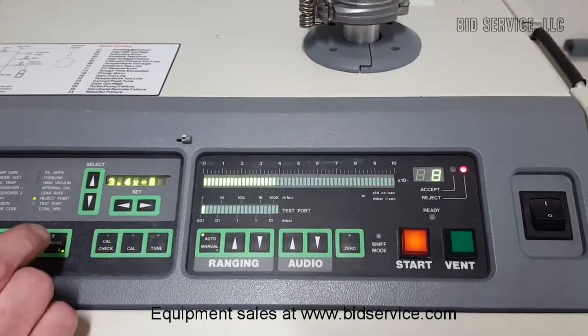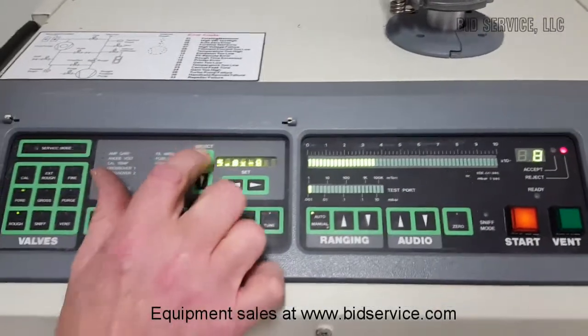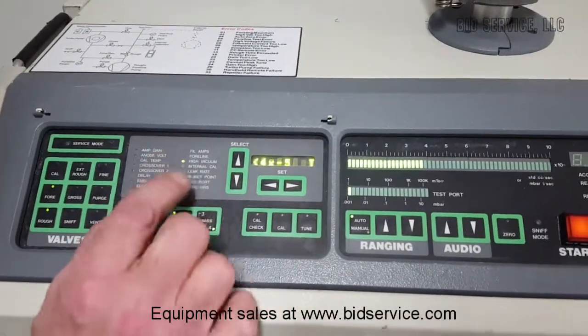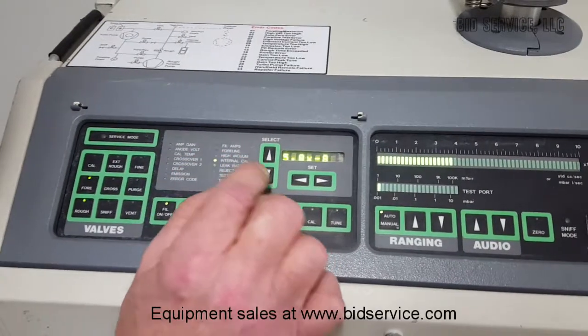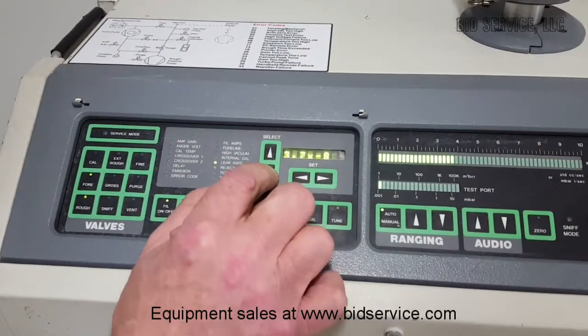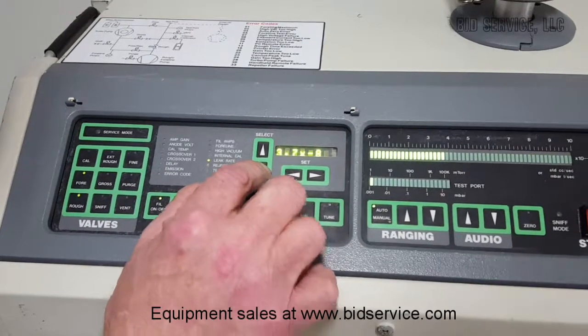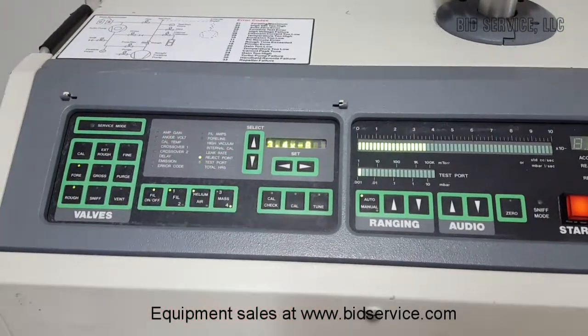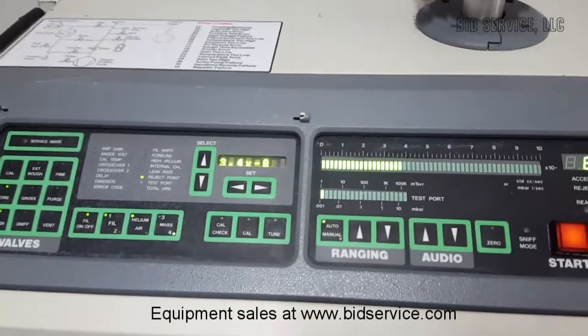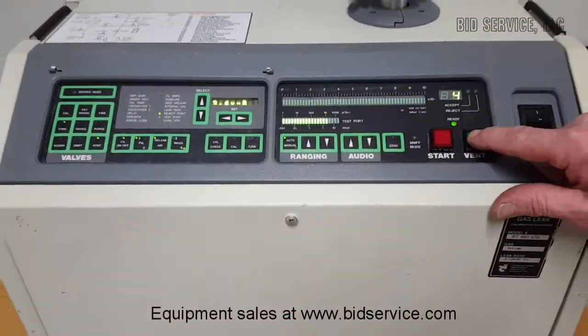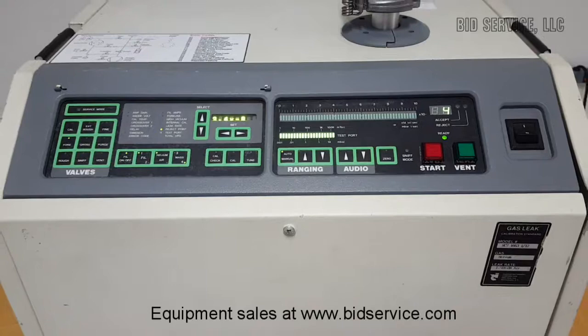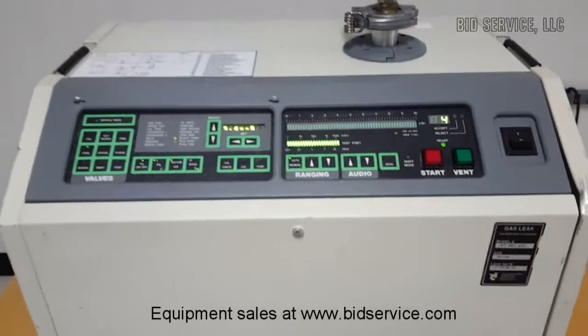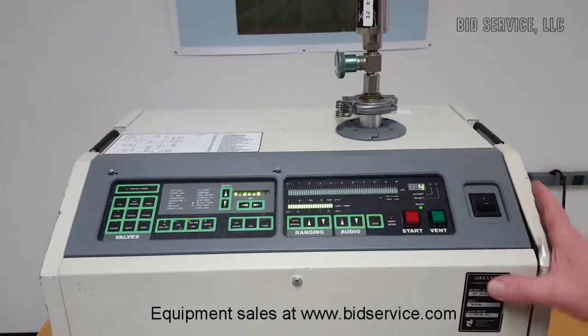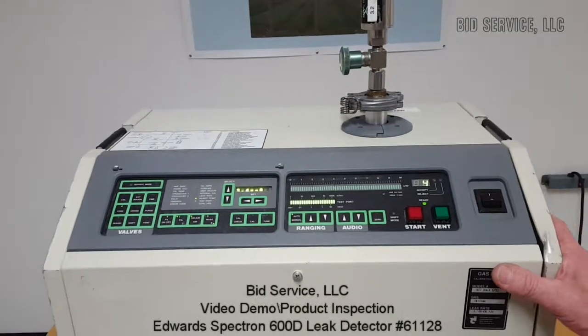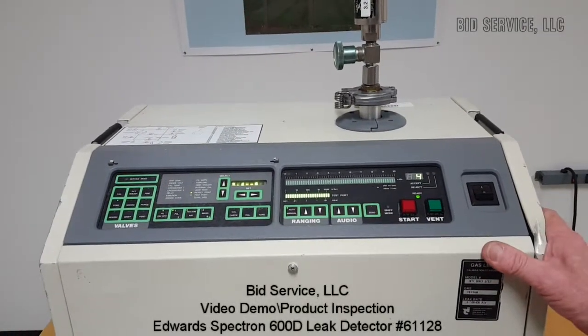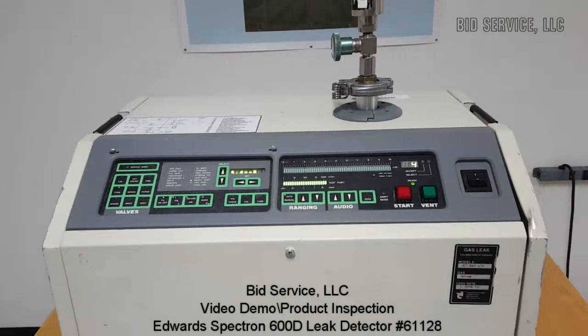I like that. It will also tell you some of the status of your high vacuum system, your internal calibration, and very importantly, your leak rate, and of course your reject point. It's very easy to use. It's a convenient portable unit that fits on most bench tops without a problem. And this completes this demonstration.